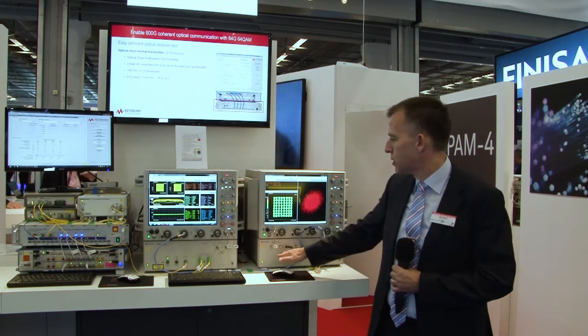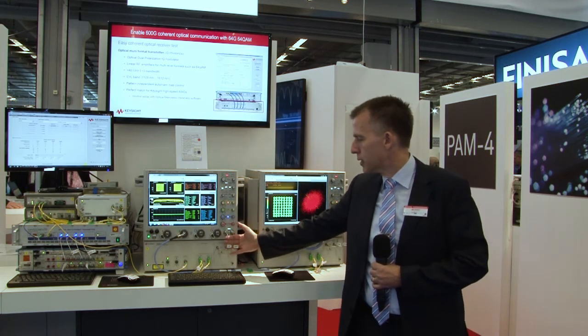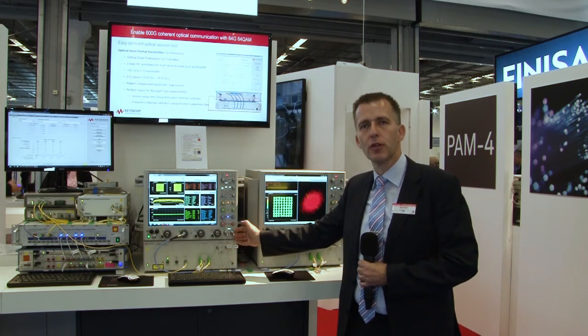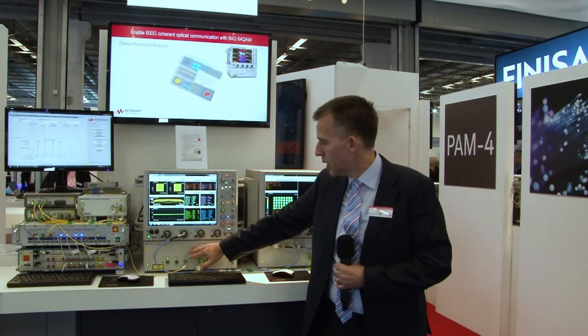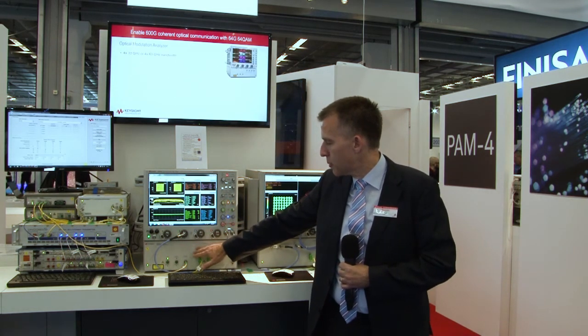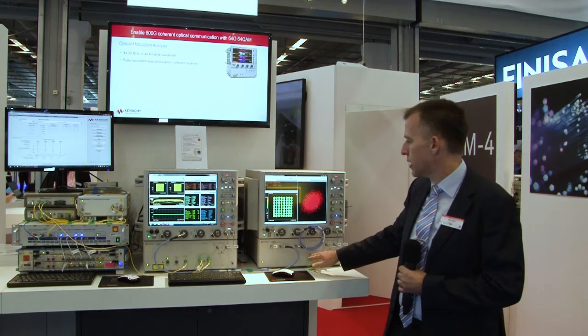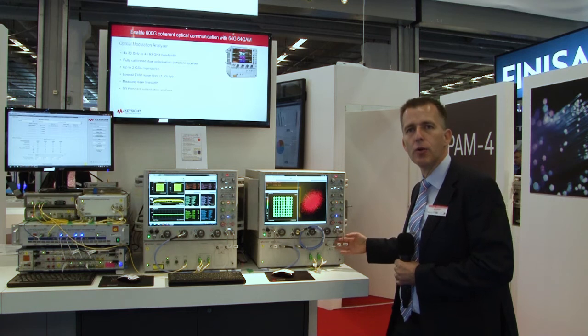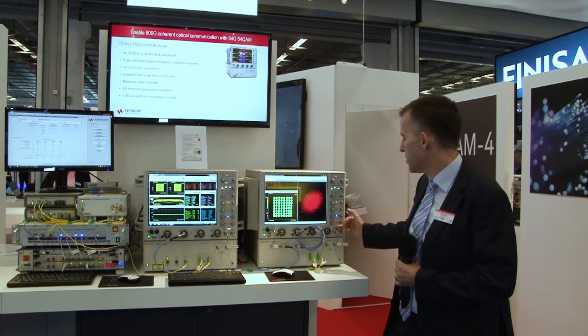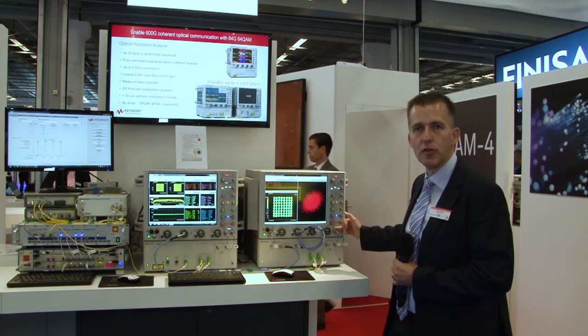The reason why we split it up into two pieces is to keep the electrical signals from the photo receivers to the oscilloscopes as short as possible. There's an optical distribution between the primary test set, as we call it, to the secondary test set where we have again another pair of photo receivers providing the O2E conversion to be analyzed by the oscilloscopes.